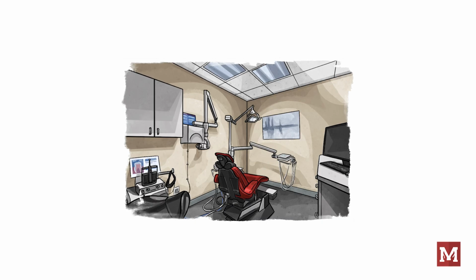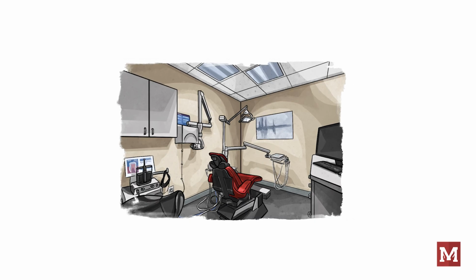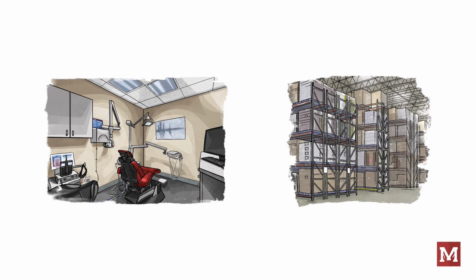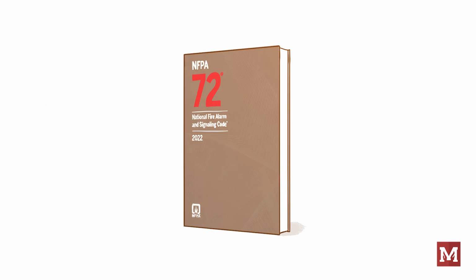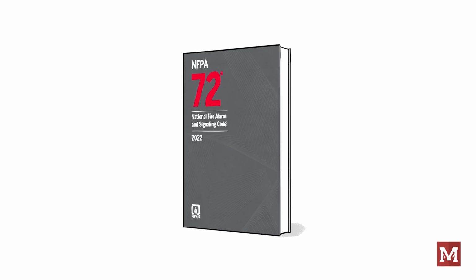Would we possibly need to add more strobes if we're standing in the middle of a warehouse aisle with 25-foot racks and we can't see any flashing light when the fire alarm system's activated? Yeah, we would. Each of these requirements come from NFPA 72, Chapter 18. We get requirements for install, locations, strobe coverage, pulsing, flashing frequency, and synchronization.